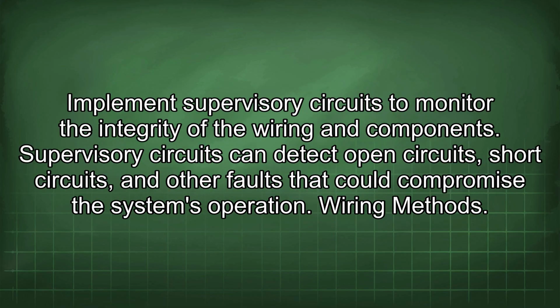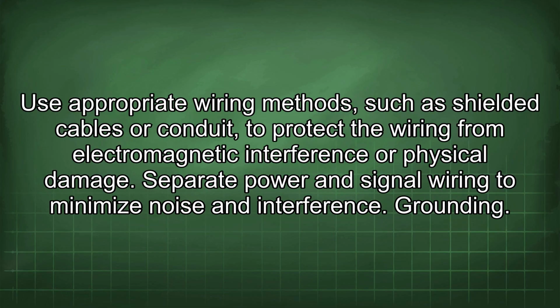Supervision. Implement supervisory circuits to monitor the integrity of the wiring and components. Supervisory circuits can detect open circuits, short circuits, and other faults that could compromise the system's operation. Wiring methods. Use appropriate wiring methods, such as shielded cables or conduit, to protect the wiring from electromagnetic interference or physical damage. Separate power and signal wiring to minimize noise and interference.